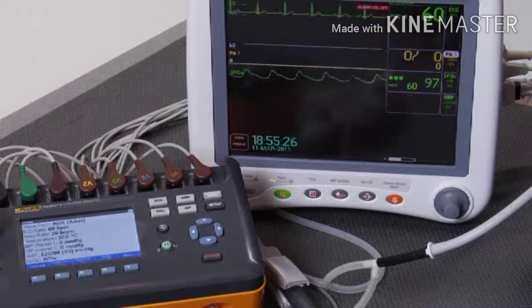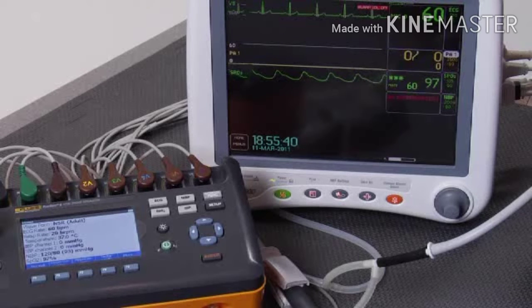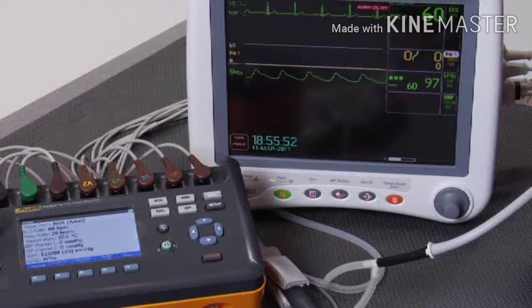not. So as I begin the test, we are already connected to the device under test. All of the connections have been made ahead of time, including the NIBP cuff. And we are going to zero our invasive blood pressure transducers on the patient monitor at the very first step of what we do, followed by a selection of a simulation of all coordinated patient parameters.